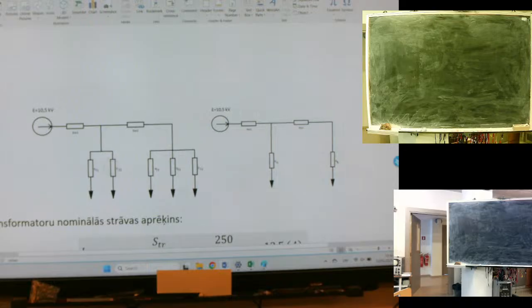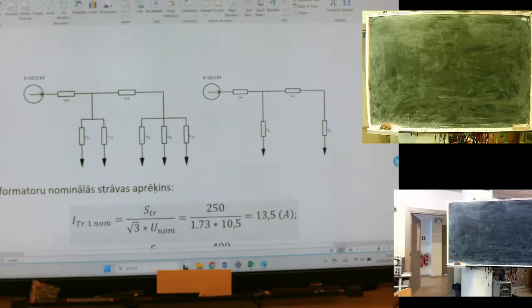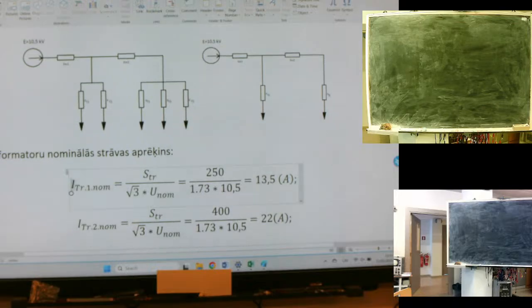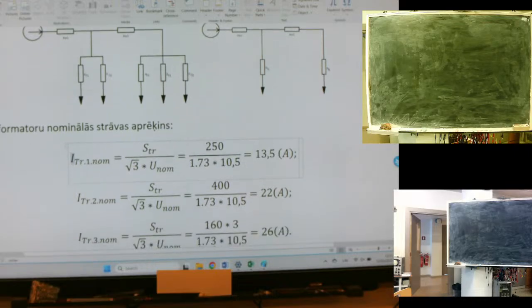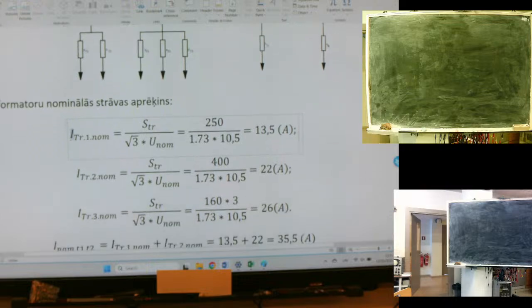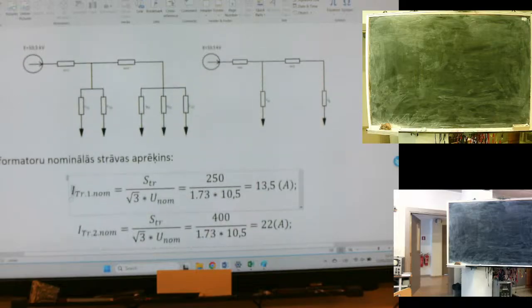Okay, so first of all, we start with the equivalent scheme. We replace lines with equivalent reactance, and transformers with reactance or impedance based on one parameter, because we understand that there is a huge difference between resistance and reactance for transformers. That's why very often we could use only the reactance, not the impedance, for the transformer. So first step, we calculate the nominal current for the transformer using the Ohm law. Very simple. When we know the transformer power, we have the nominal voltage and the Ohm law.